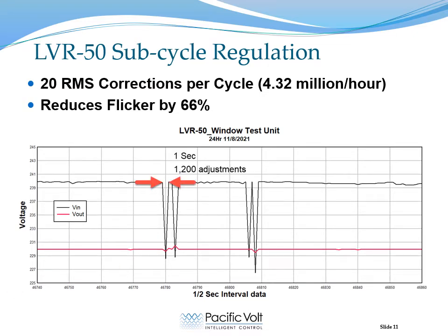It's a little bit difficult to comprehend 4.3 million corrections an hour. If you look at just one of these events, which lasted 1 second, the regulator made 1,200 adjustments during that 1 second. This helps put into perspective how the regulator can compensate for flicker.